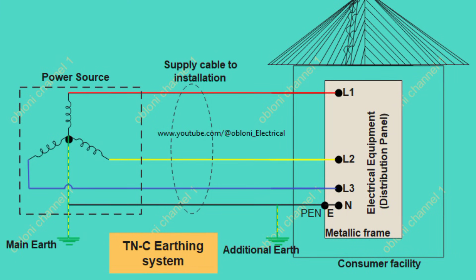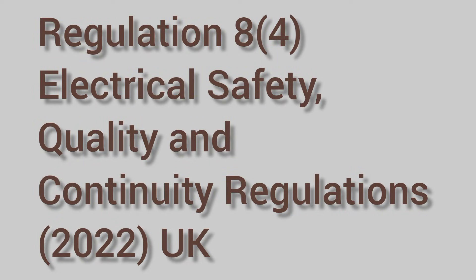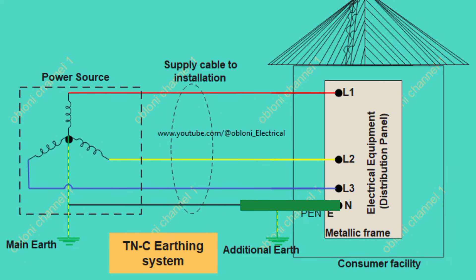The TNC earthing system. With the TNC system, the neutral and earth functions are combined in a single conductor called the PEN conductor — PEN means protective earth and neutral — throughout the entire installation. All exposed metal parts of the installation are connected to the PEN conductor. In this system, the PEN conductor is earthed at multiple points, and an earth electrode may be necessary at or near the consumer installation. However, this system of earthing poses some safety concerns to the consumer.